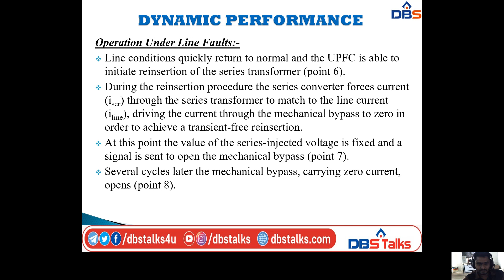Several cycles later, the mechanical bypass carrying zero current opens, that is at point 8. So the bumpless reinsertion of the series transformer into the line is complete at point 9.